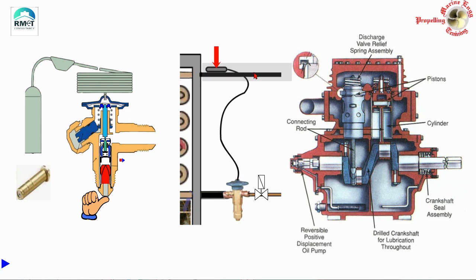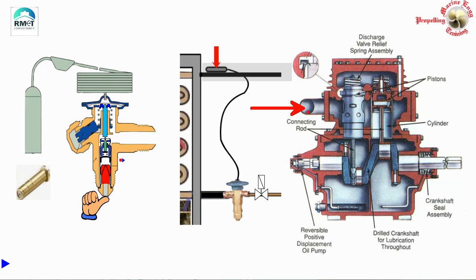Now let us move on to the next topic: liquid returning back to the compressor. The fact remains that liquid should not return, but the reasons people associate with this phenomenon may not be fully accurate. Many people presume the general feeling is that when liquid enters, it will go into the piston and break it — which is actually not true. Liquid entering the compressor from the suction pipe may have some liquid particles; it is not entering the cylinder directly but may get accumulated at a point. The real issue is that the refrigerant communicates with the crankcase and they are at the same pressure — and that is where the damage occurs.